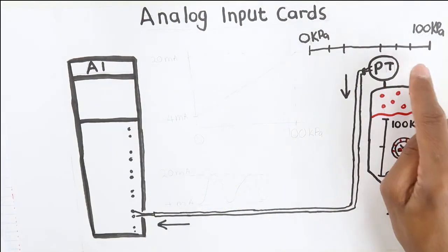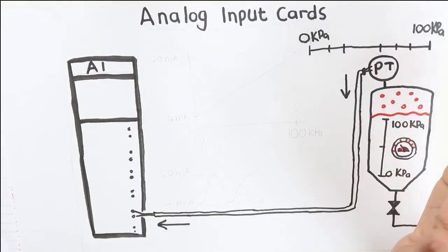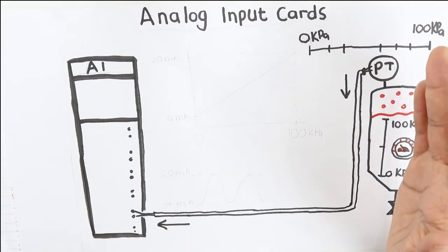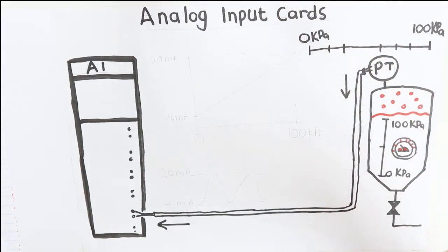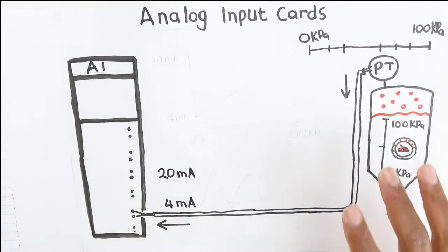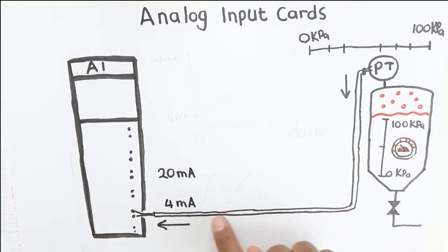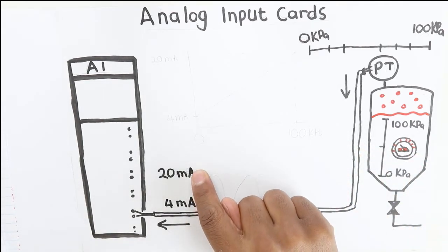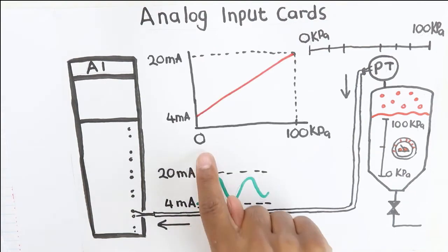Now how the pressure transmitter does this is a very interesting phenomenon which is a pure definition of mechatronics, but I will not go into that now. The most common electrical signal for transmitters is the 4 to 20 milliamp signal. This means that the pressure transmitter will map this 0 to 100 kPa pressure value to the 4 to 20 milliamp signal.